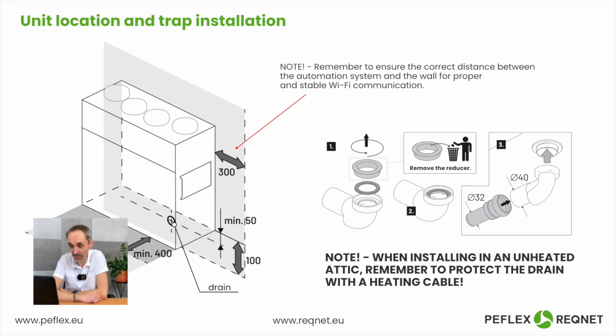Another important issue is the space around the recuperator. We need to leave enough adequate service space for the proper and efficient maintenance of the device, but also enough ample room, among other important things, to easily access the critical control automation board. I've had situations where clients called me about an issue with the automation, for example, when a Wi-Fi module reset was needed, but the distance from the wall was only 10 centimeters, making it impossible to get a hand in or do any work at all. That's exactly why we recommend leaving enough space so that the work can actually be done. So, read the instructions again and follow the recommendations.